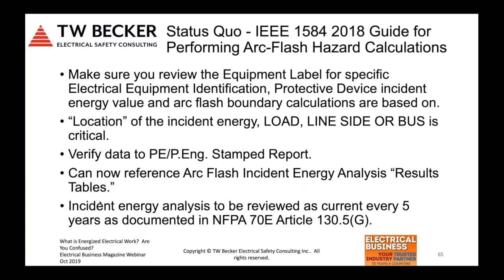As well, Z462 and NFPA 70E allow the arc flash information to be provided using other methods now. Results tables can be posted by the owner of the electrical equipment. And the 5-year review of the incident energy analysis study is still valid. So I'm telling industry that the formulas have changed. You don't have to panic.